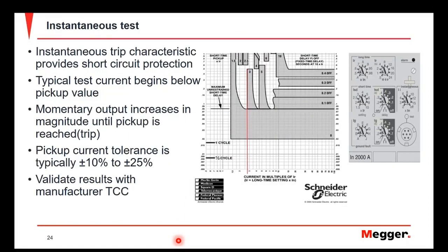The instantaneous test is a pickup test performed using a momentary current output. We start below the pickup point for the instantaneous setting, then pulse current in increasing magnitudes until the breaker trips — that's the pickup point. We record the current value at which the breaker tripped. For electronic trip unit breakers that value is typically plus or minus 10% of the pickup value; for older molded case breakers, the tolerance could be as much as plus or minus 25%.